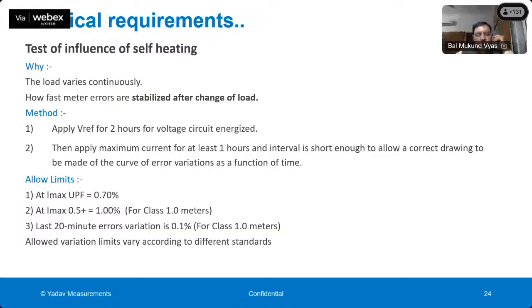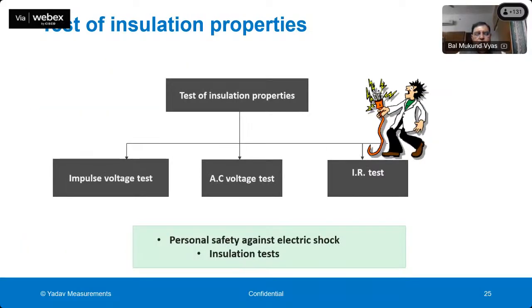In this test, initially the meter is powered up for 2 hours without any current, and then accuracy is tested. After that the maximum current is applied to the meter at UPF and also at 0.5 power factor, and then the accuracy of the meter is tested every 20 minutes until it gets stabilized, and the variation is checked. So you can see the various tests it has to pass through.